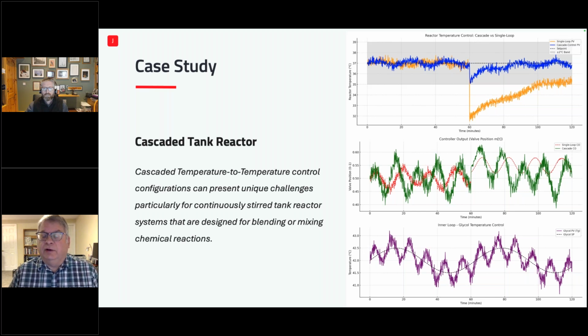So the upper plot there is the actual process variable. The blue one is essentially the primary process variable that I'm trying to protect. That's the reactor temperature. And then the yellow, and by the way, these are two different scenarios, Damien. The first one is just running kind of normal, we're at temperature. And then the second half of that graph, I just smooshed them together. The second half of that graph is where the disturbance has already knocked us off.